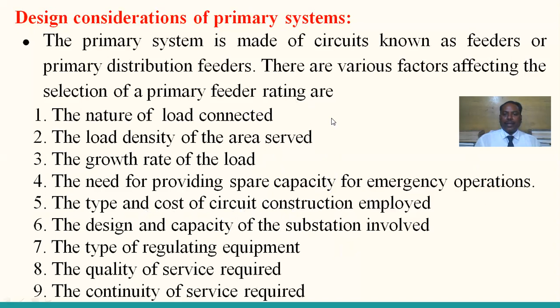So let us go to what is the primary feeder. You see here. This is an 11 kV substation bus. The 11 kV substation bus is initiated in the substation. From there onwards, the outgoing feeder passes through a circuit breaker. A circuit breaker is an automatically operated device. The outgoing feeder, passing through the circuit breaker, continues going and covers large distances. This is the primary feeder.